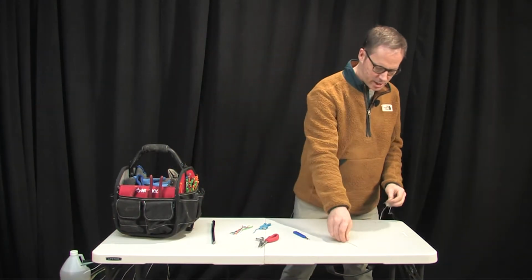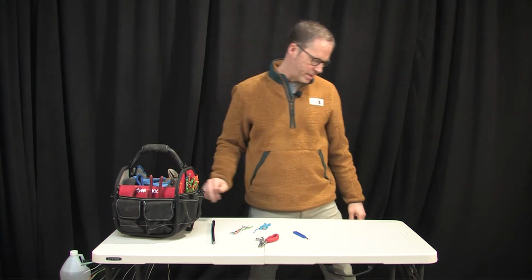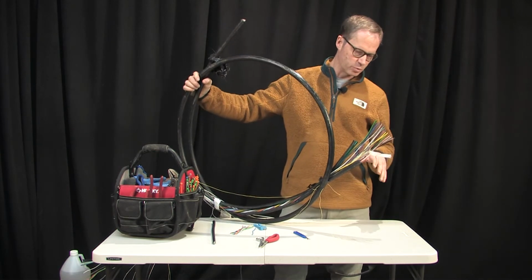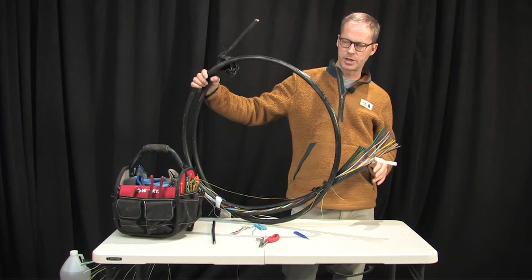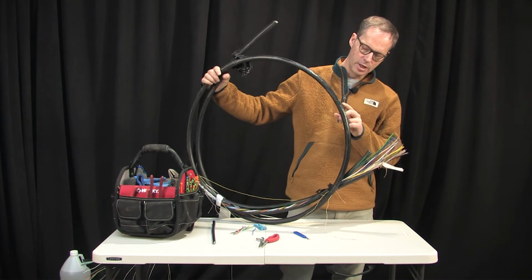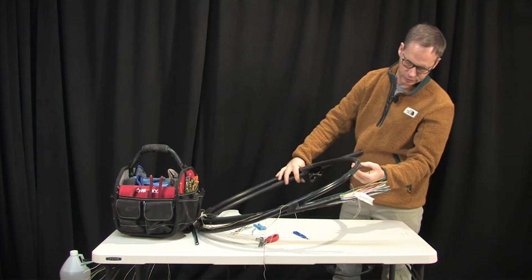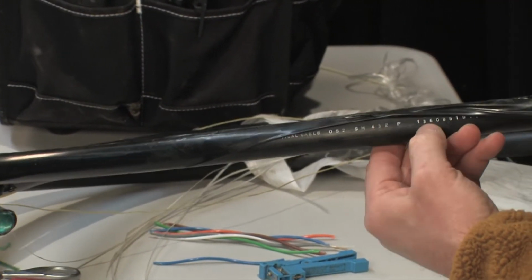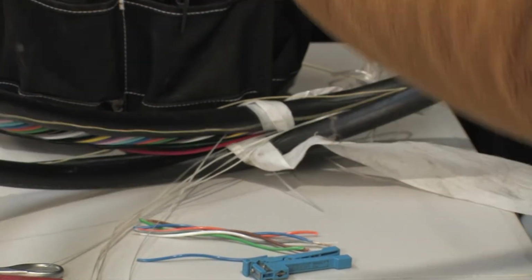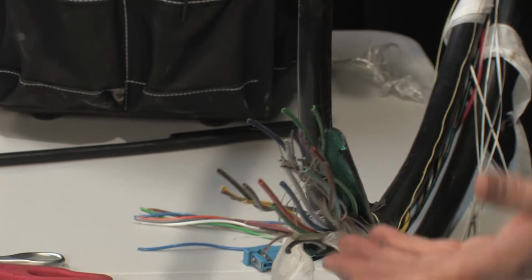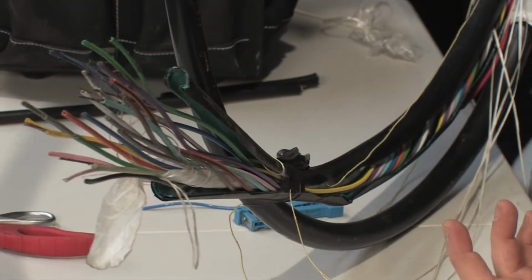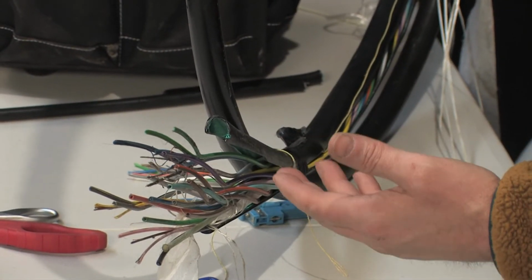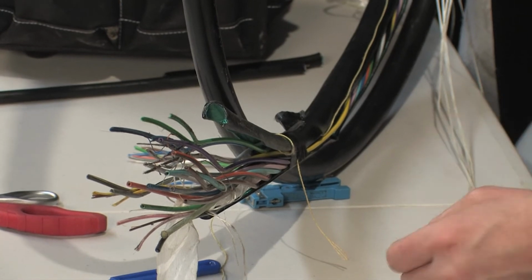One last fiber that I want to show you is a rather massive fiber here. We're not talking about ribbon fibers just yet, but this particular cable is a recent project that we just worked on. It'll be some of the projects that we'll be working on over the next couple of years. If we look at this number here, you'll see that it says it's a single mode 432 count fiber. So looking at this number, what we can expect to see inside the cable is, instead of 12 fibers per buffer tube, this happens to be a 24 strand per buffer tube, and this is also a gel-filled cable.